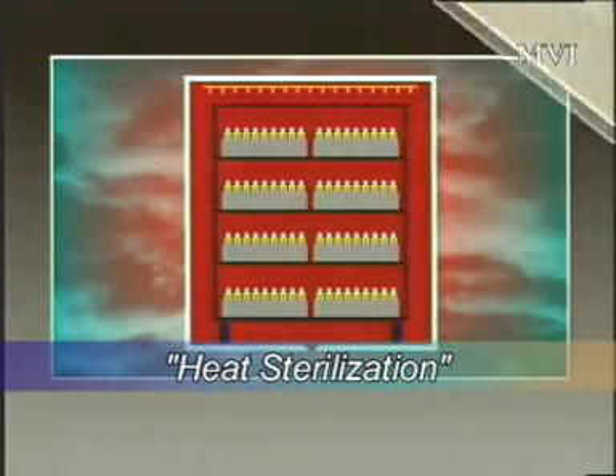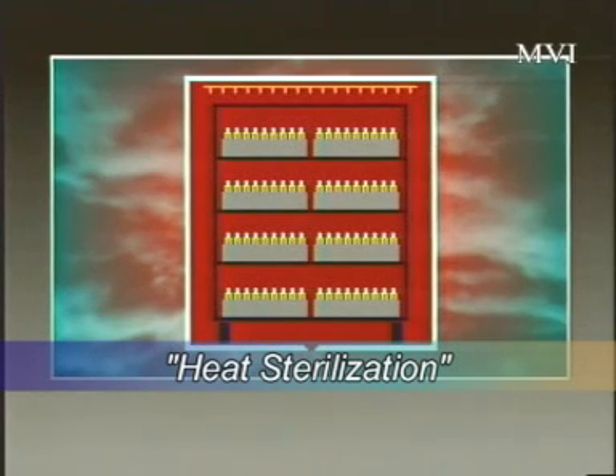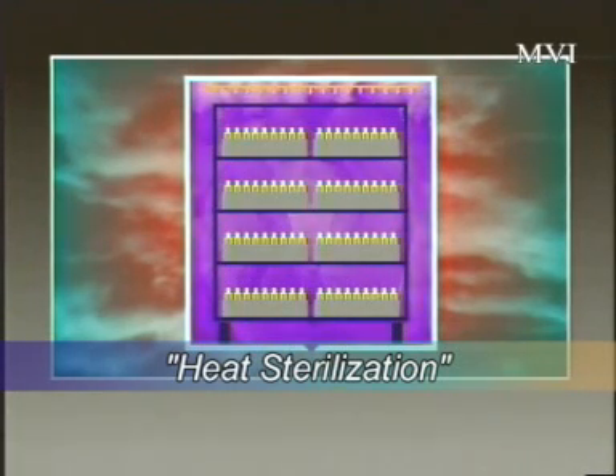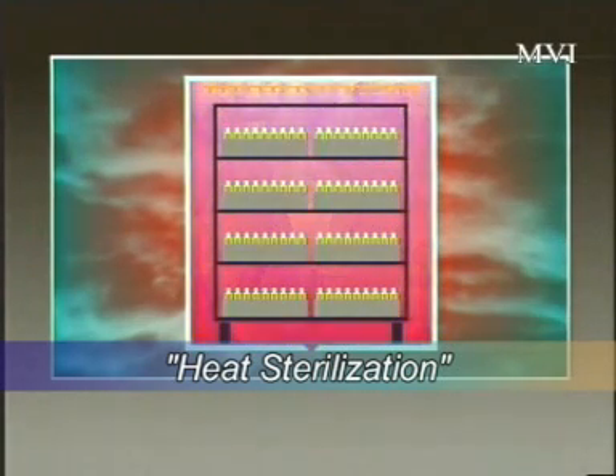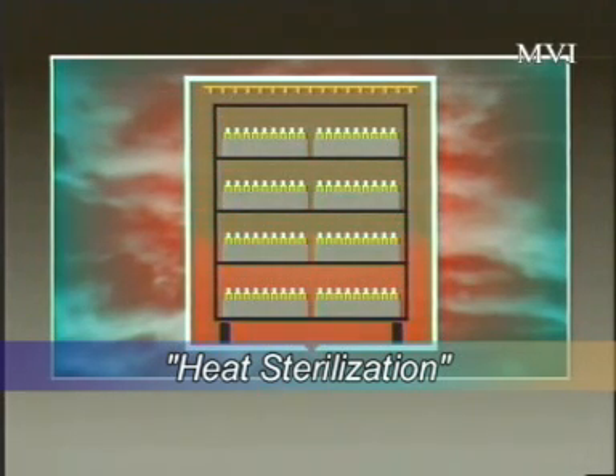At completion of the sterilizing stage, a vacuum is created in the chamber so that the condensate, the water formed as steam cools and forms on the surface of items being sterilized, will boil off as the chamber pressure reduces. Finally, air flows into the chamber through a biological filter until atmospheric pressure is reached, and when the temperature is safe, the load is removed.